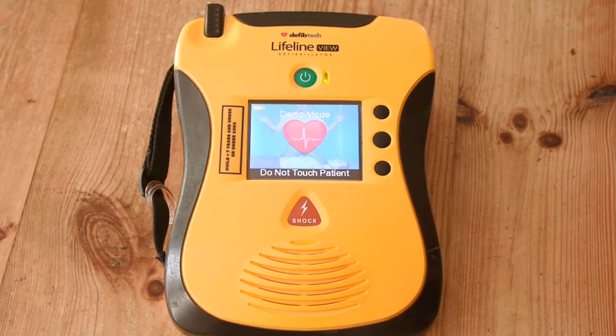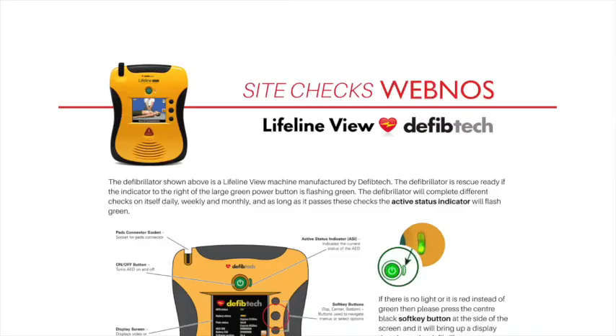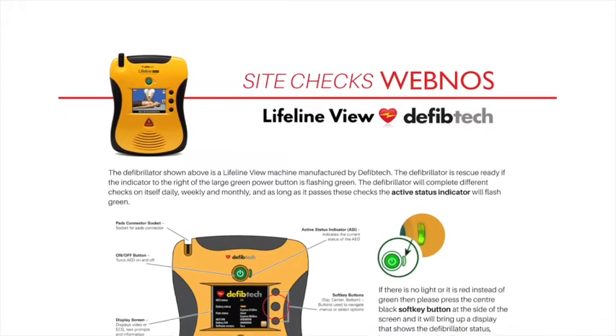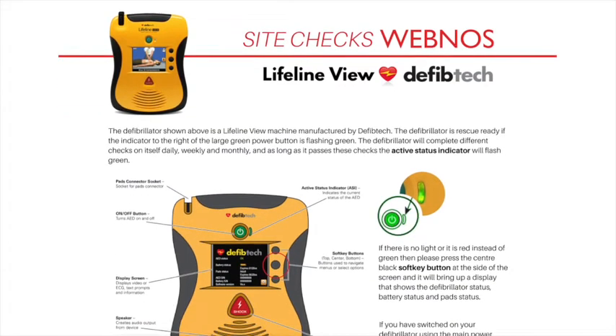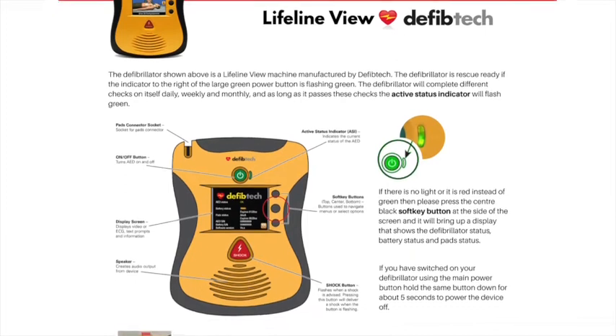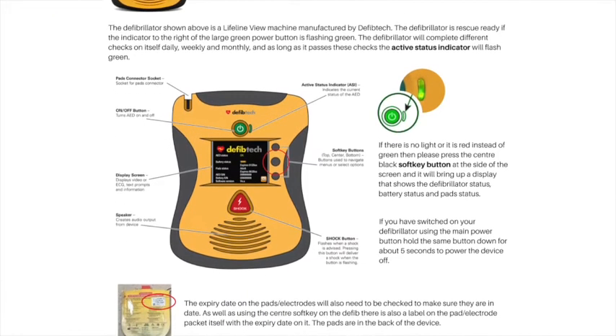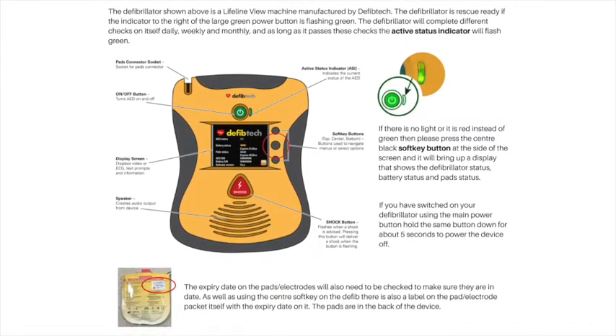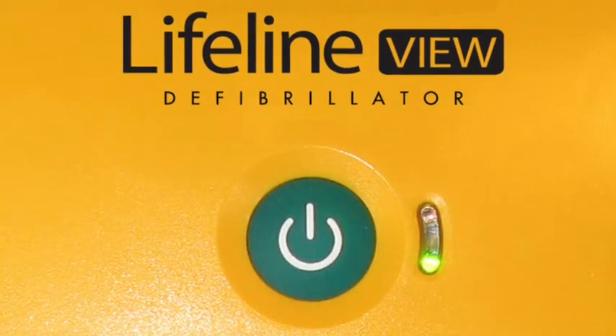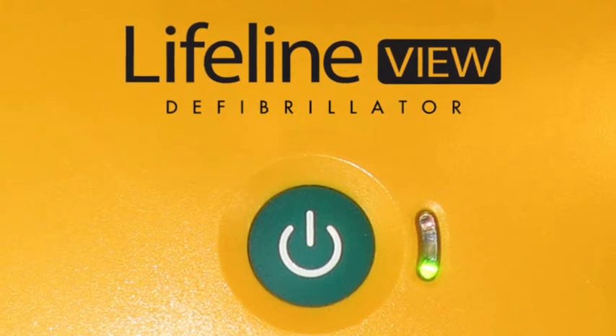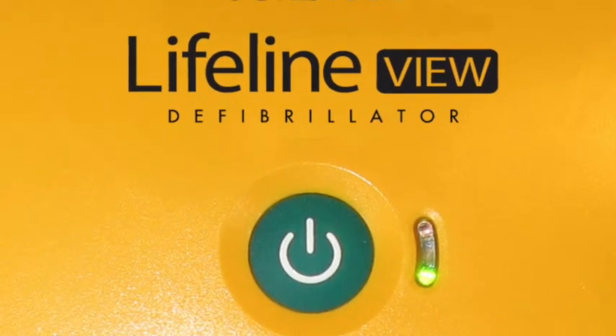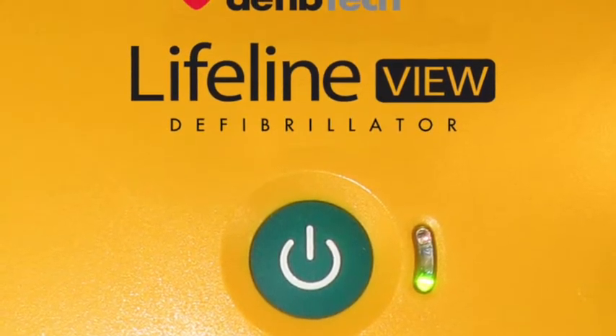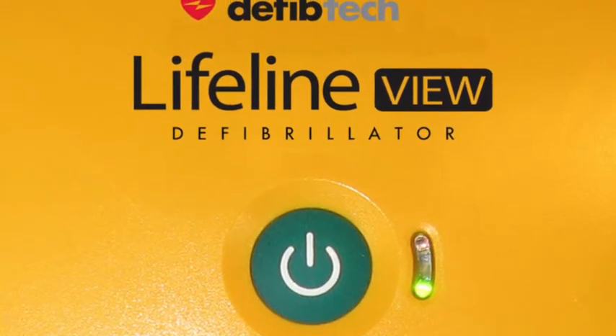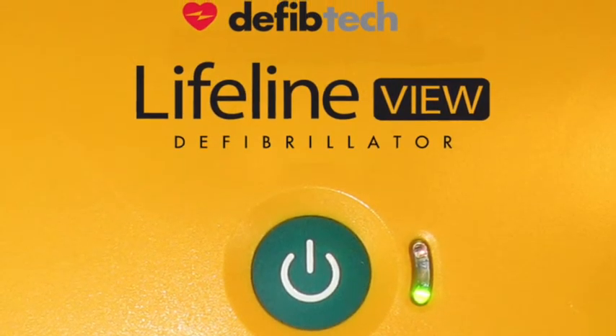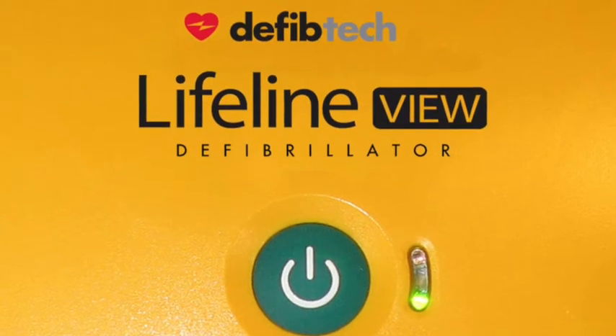We have also provided you with a simple instruction sheet on how to do the checks, which you can refer to if you like. The defibrillator checks itself every night, and also a larger, more detailed self-check every week. If it finds anything, it will tell you. The green light will change to red, and the error it has found will display on the TV screen. You may need to press the middle black button to get more details, and then use the Report a Problem on Webnos to tell us what the issue is, so we can resolve.